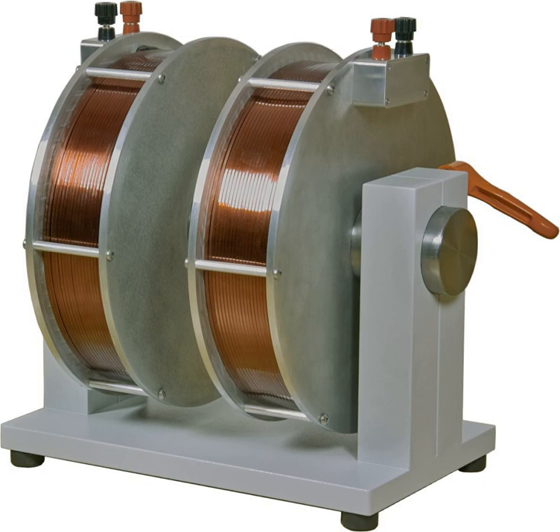Topic: Ohmic heating. The only power consumed in a DC electromagnet under steady-state conditions is due to the resistance of the windings, and is dissipated as heat. Some large electromagnets require cooling water circulating through pipes in the windings to carry off the waste heat. Since a magnetic field is proportional to the product Ni, the number of turns in the windings N and the current I can be chosen to minimize heat losses, as long as their product is constant.